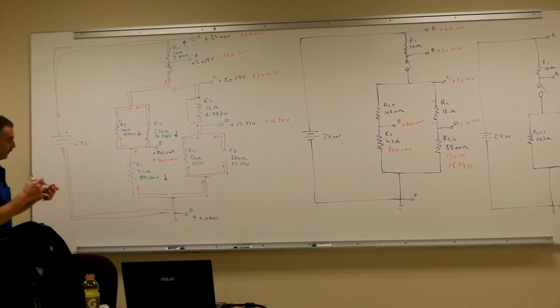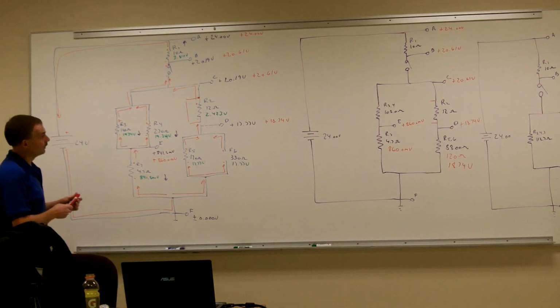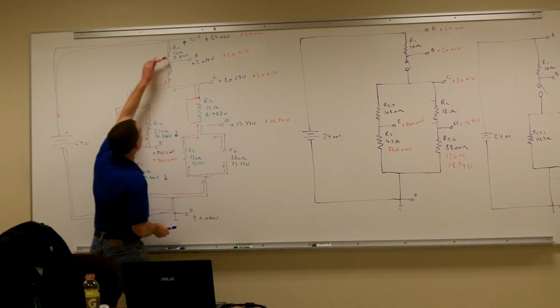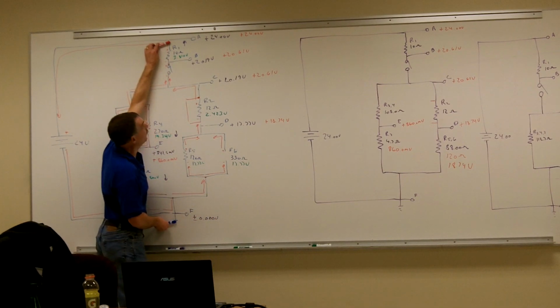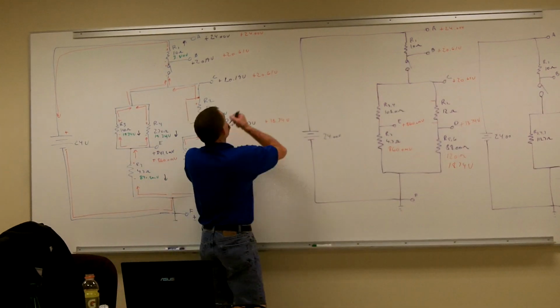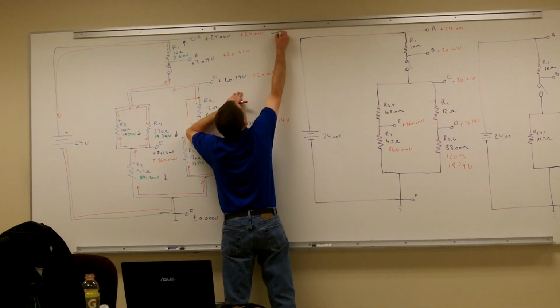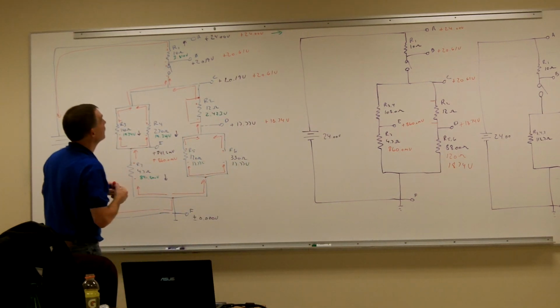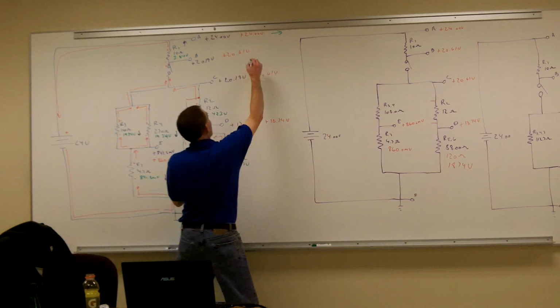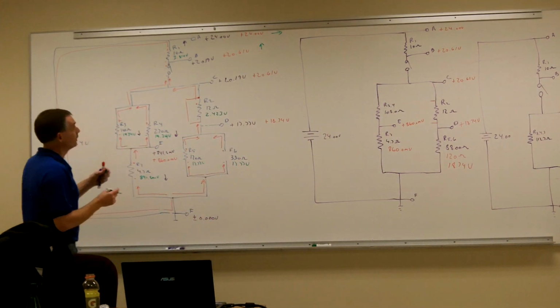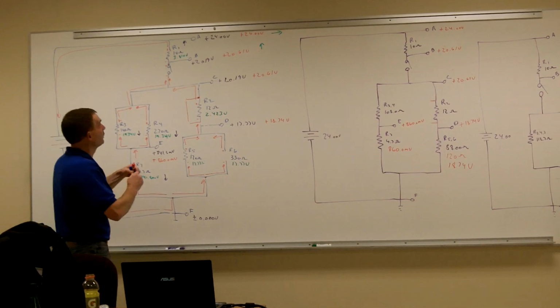All right, so there's our new test point voltages. We know that test point A to ground, we still have our positive 24 volts, so that one's remaining the same. Test point D did what? Increase or decrease? Increase. So since we know that our voltage increased, we know that we probably have some open now.